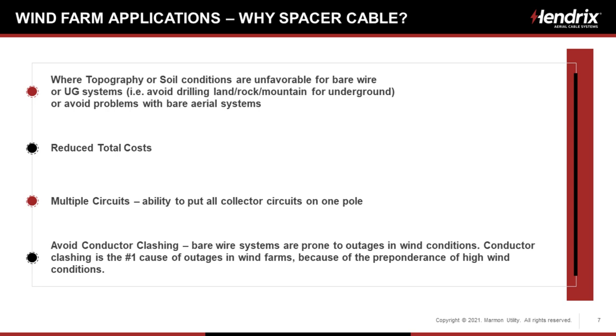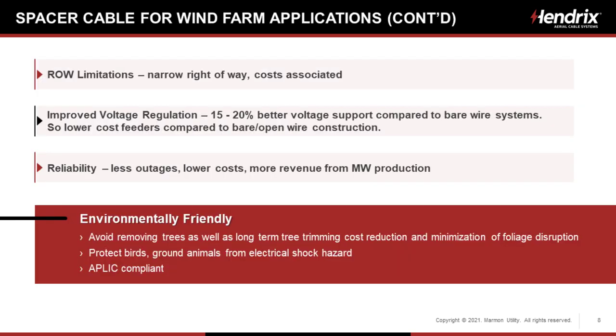We're going to have reduced total costs. We're able to put multiple circuits all on one pole. And we're going to avoid conductor clashing. We know that with wind farms, conductor clashing is the number one cause of outages in this wind farm. So it leads not only to loss of reliability, but massive loss of megawatt output and revenue. At wind farms, we expect high winds. So it's something we learned after the first several years of large wind farms, but it's significant. And with spacer cable, you don't get conductor clashing. And if you do, there's no outages.